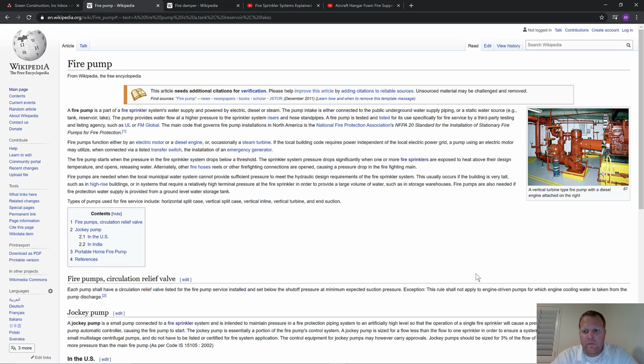Another part of fire suppression systems that I think is important to at least have some basic understanding of is the actual fire pump. Many buildings are running just off the city pressure, or the municipality's water pressure, and that water pressure is coming into the building. If a sprinkler goes off, that's the pressure it's using, basically city water, right? The water pressure in the city to go extinguish the fire, or maybe not extinguish it, but to provide suppression.